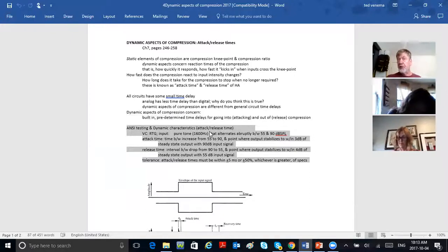I think a third one was reference test gain, showing you what the hearing aid is doing with the user settings, like with the volume control reduced. And then you had equivalent input noise, like how much noise is the hearing aid making inside? What's the noise of the hearing aid? Okay, and that had a tolerance of 3 dB. And then you had harmonic distortion.